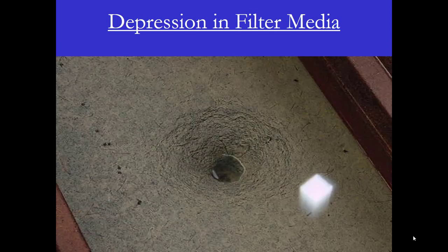One of the best ways to start a filter inspection is to drain a filter after a filter run. It's then that you might notice some problems with the filter, such as a depression in the filter media.